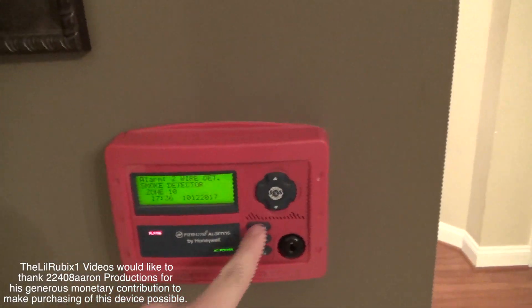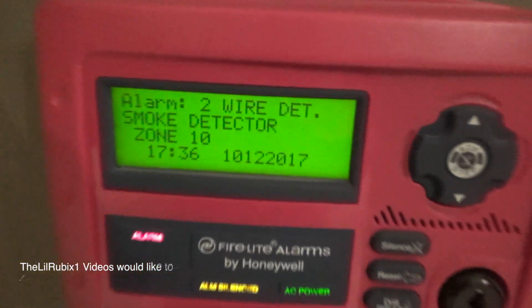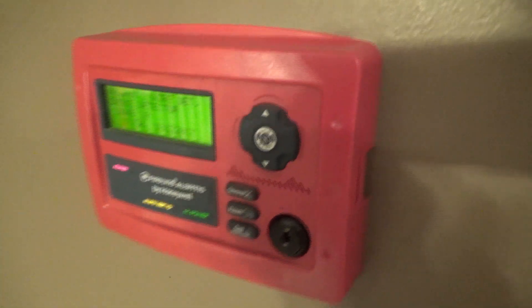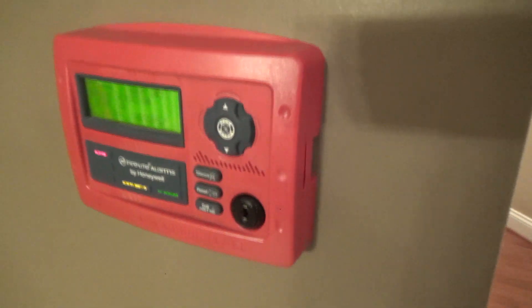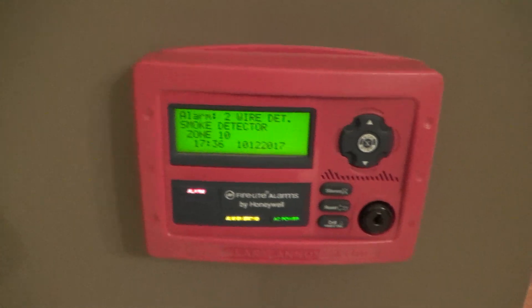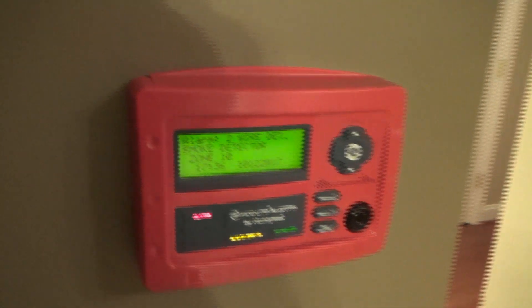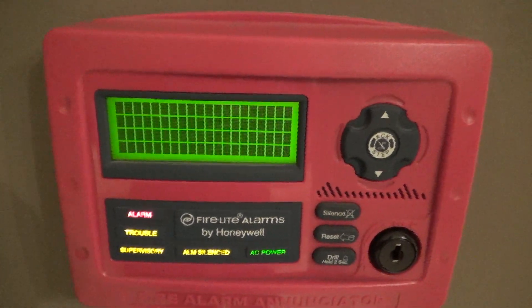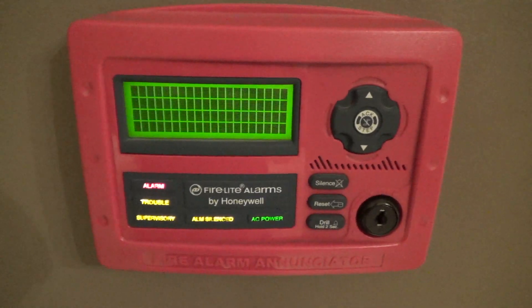We're going to use the newest addition to our system to silence the alarms. This is our new Fire-Lite ANN-80 annunciator, which goes of course right to the MS-10UD. I'm really happy with how this looks and its functionality. Go ahead and reset it — it looks really strange when it does that. Hopefully if the smoke is cleared it should not go right back off.